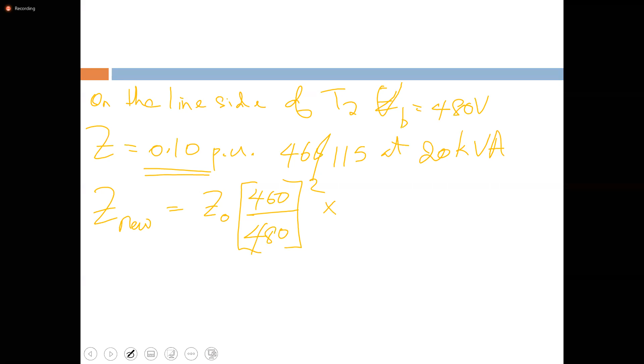So Z new is equal to Z old, and I said you start with what? V old. What is V old, the voltage of the transformer on the line side? 460. And 460 would be the old base. What's the new base we are converting to? 480. Squared, times the new S base, 30 kVA, over the old one, 20 kVA.